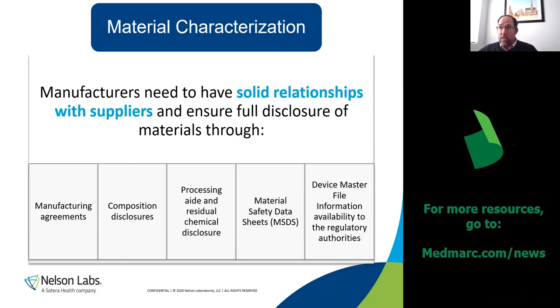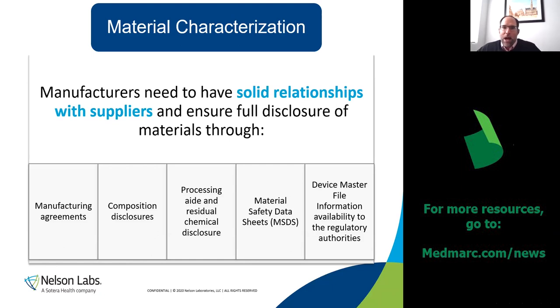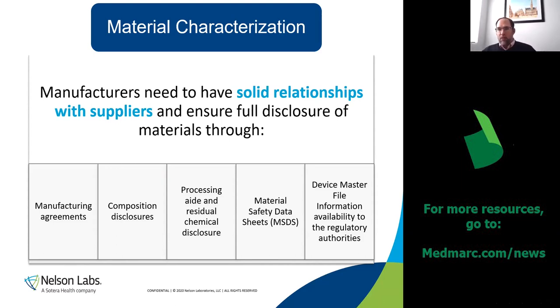As toxicologists, we love composition disclosures. If you tell us what's in the material — what stabilizers, UV stabilizers, and additives are in the plastic — I can actually do better at predicting the safety of that device to the patient. Unfortunately, we usually can't get that information from suppliers due to IP concerns. But along with that, you also need to know what possible residuals might be on their materials. They may tell you it's silicone, which is great, but what are they using during their manufacturing process? Are they cleaning it with a detergent? We need to know what residuals could be on that material that are now on your device.